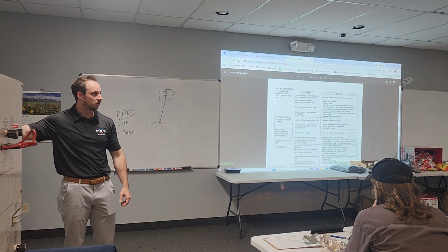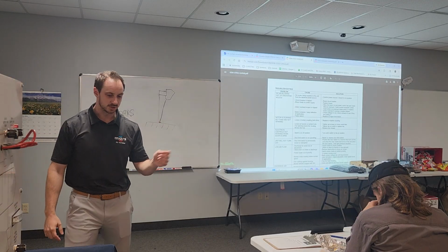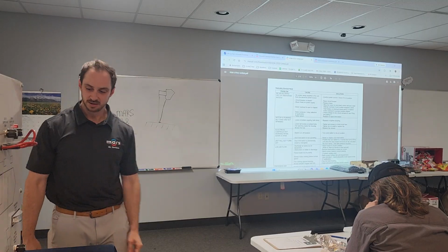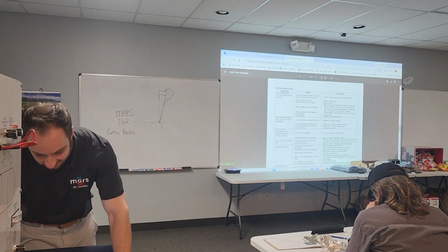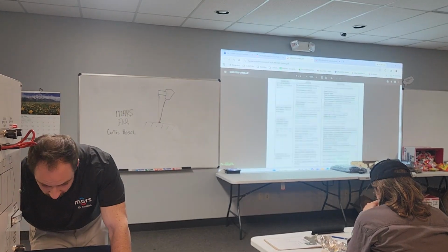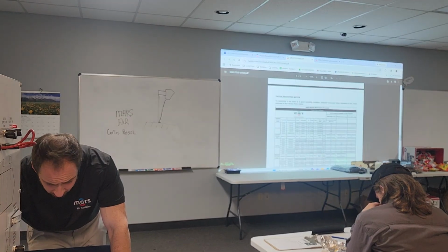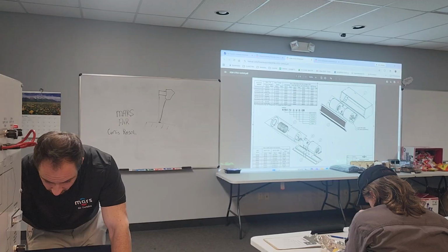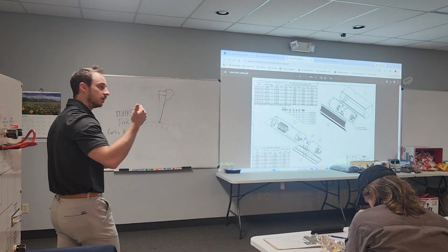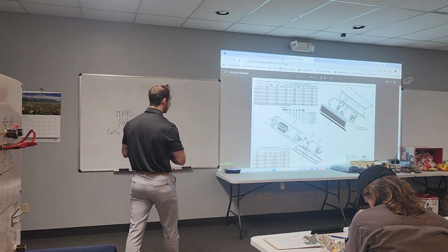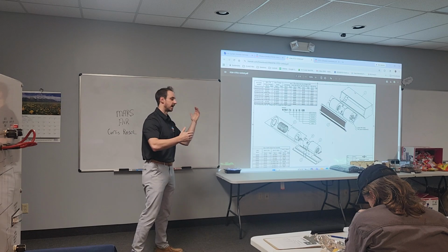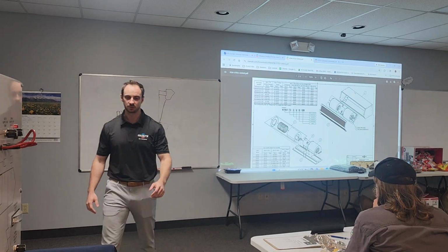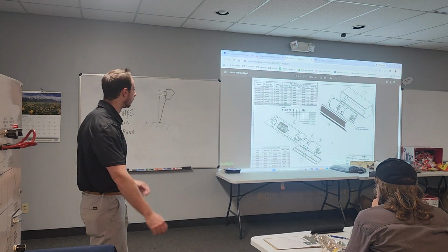If you just hold it along the door, you see the fluctuations, and you just want to make sure it's not pulling it out of your hand. There's some troubleshooting here. We do have a startup checklist as well. I don't believe it's in the IOM, but you guys can reach out to Gardner for that. We have that internally. It takes you through a typical checklist to make sure everything's up and running properly.